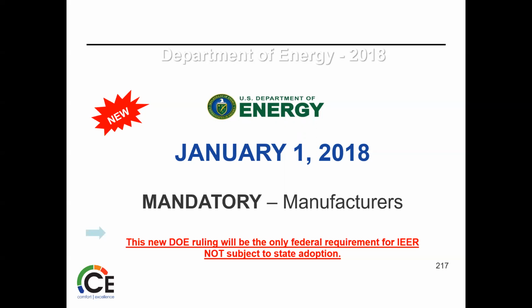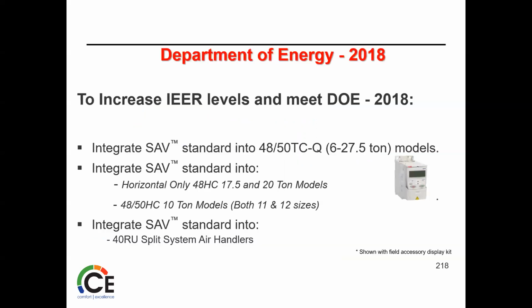Units built in 2017 can be sold in 2018 and beyond in the US, but we have to increase the IEER levels and meet these requirements. So we've integrated this staged air volume standard within these models. And the way that we had to do that was to introduce a variable frequency drive to take a single speed fan and turn it into a 2-speed fan.